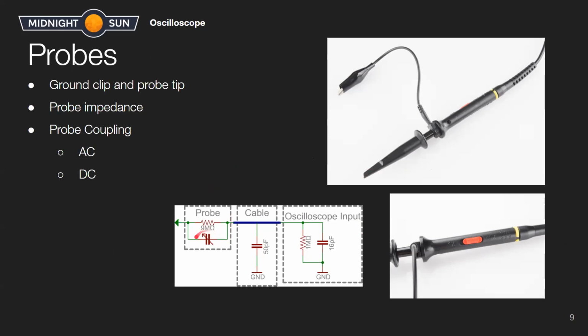The other thing to notice here is that there's an adjustable capacitor in parallel with the probe resistance, and this is to help compensate the probes. This is to make up for all the other parasitic capacitances in the probe and the cable and the oscilloscope. I'll talk about that on the next slide, but that capacitor can be adjusted by turning a screwdriver in this little hole here. There's a better image on the next slide.